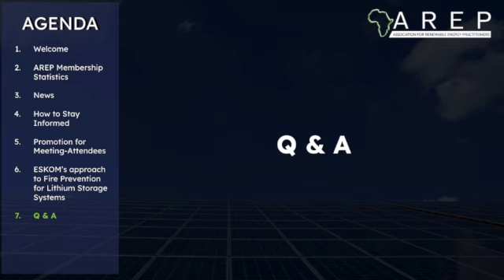The burning will still continue. I've seen tests where they force a battery into thermal runaway, empty a CO2 fire extinguisher on it, and when you take it off, it just continues burning. So typically, CO2 is used on electrical equipment. DCP, the dry chemical powder extinguishers, can also be utilized, but then you have a residue—a fine powder that ends up over all the electrical equipment.